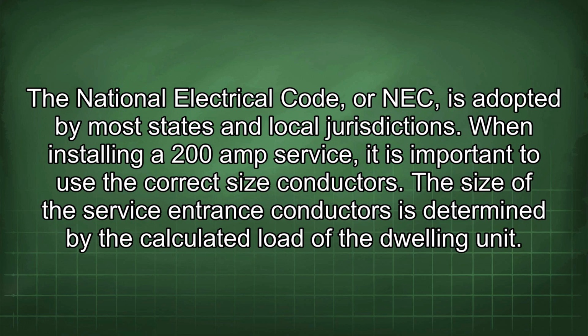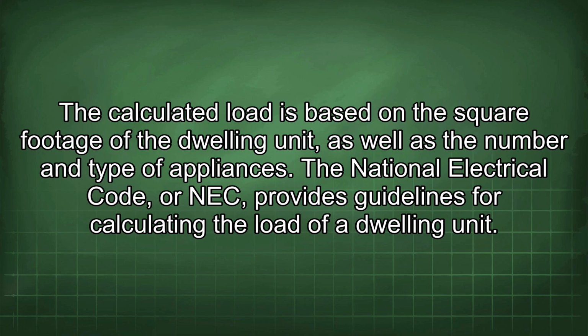When installing a 200 amp service, it is important to use the correct size conductors. The size of the service entrance conductors is determined by the calculated load of the dwelling unit. The calculated load is based on the square footage of the dwelling unit, as well as the number and type of appliances. The National Electrical Code, or NEC, provides guidelines for calculating the load of a dwelling unit.